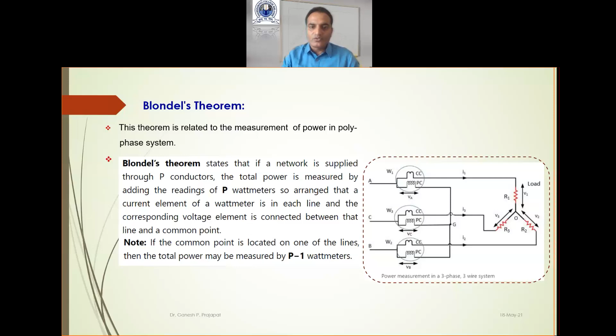Although 3 watt meter method is quite simple because you just connect the current coil of each watt meter with one of the line conductors and make the pressure coil common with one of the points. Like here, this is one of the arrangements for the measurement of power using the 3 watt meter method. So this is a three phase load.